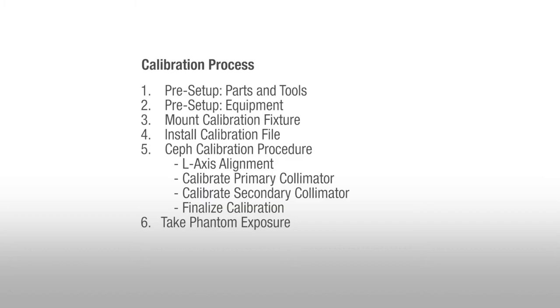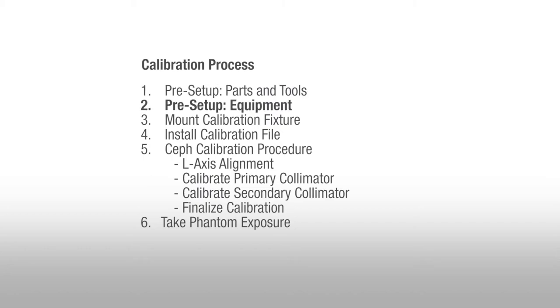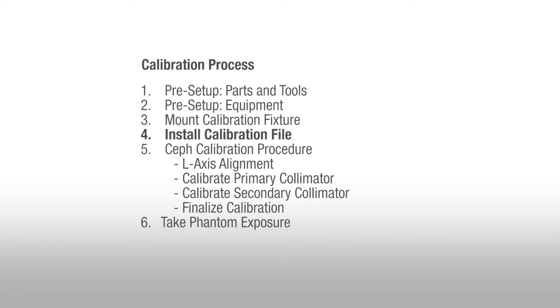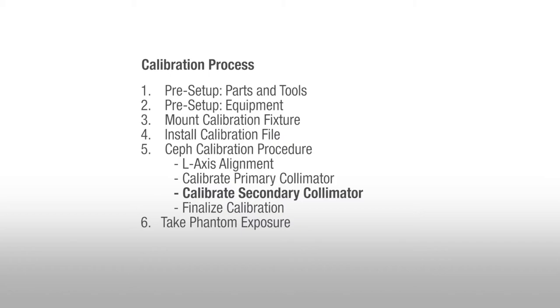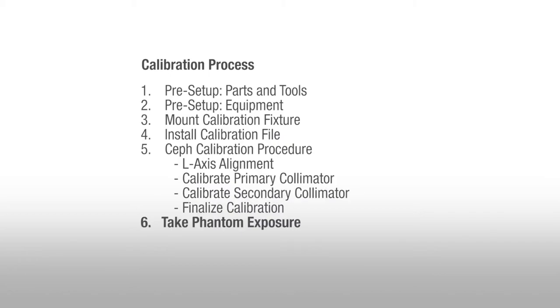Now that the pre-check is complete, we will begin the calibration process. The following workflow will be covered in this section: Pre-setup, Parts and Tools, Equipment, Mount Calibration Fixture, Install Calibration File, Ceph Calibration Procedure, L-Axis Alignment, Calibrate Primary Collimator, Calibrate Secondary Collimator, Finalize Calibration, and lastly, take a phantom exposure.